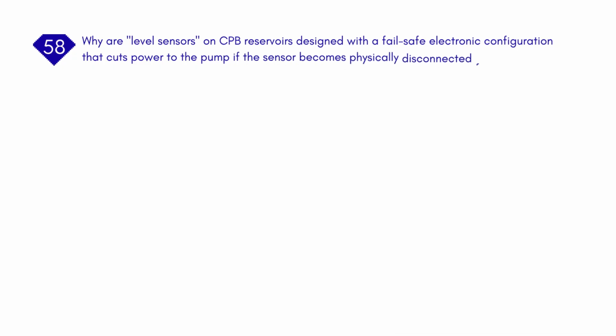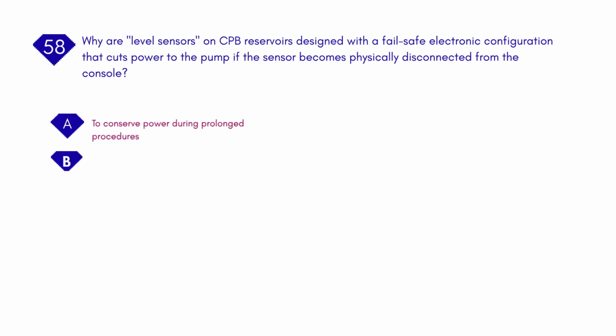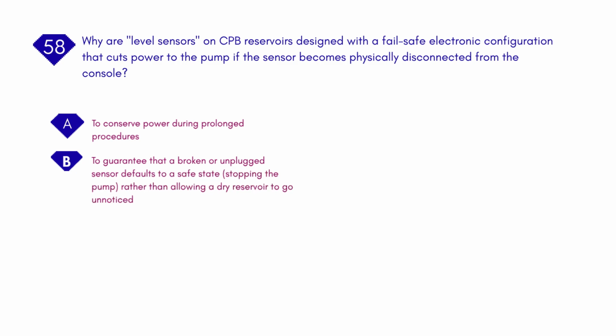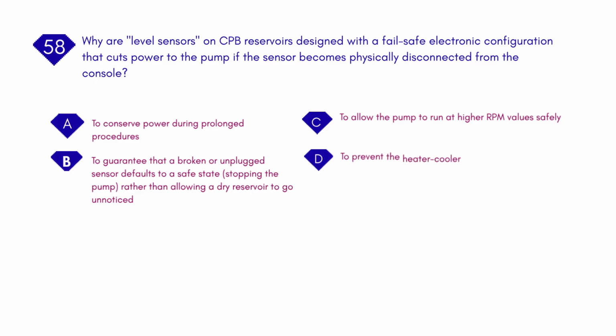Why are level sensors on CPB reservoirs designed with a fail-safe electronic configuration that cuts power to the pump if the sensor becomes physically disconnected from the console. Why? A. To conserve power during prolonged procedures. B. To guarantee that a broken or unplugged sensor defaults to a safe state, stopping the pump, rather than allowing a dry reservoir to go unnoticed. C. To allow the pump to run at higher RPM values safely. D. To prevent the heater-cooler from overheating.